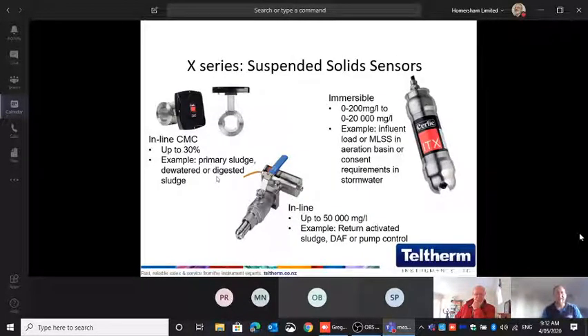These are the sensors we have from Cerlic at the moment. This is the one that we use in aeration basins, DAFs, and in stormwater drains to measure consent requirements. That unit measures up to 20,000, so 2%. So it's very easy to use at 150, 200 milligrams a liter. We do have applications where we use that unit now. Tatoa is using it now for, I think, about 4 years, and they've now standardized on Cerlic for the next upgrade that's coming.